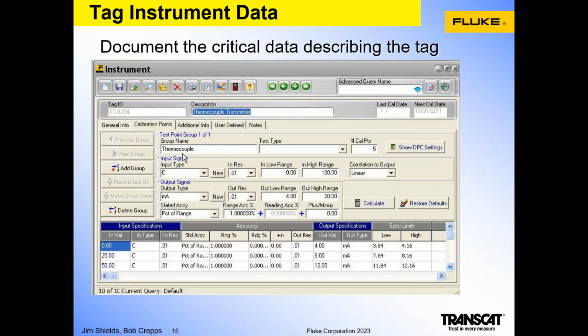Inside the information about this tag, we can see further information about its parameters. It's a thermocouple transmitter. Its input is measured in degrees C. Its output is a milliamp signal. It has a range of 0 to 100 degrees C. Output is 4 to 20. And the specification for the device, the error allowed, is in percent of range, and it has a 1% tolerance. Based on that information, you can see down below the allowable deviations for the milliamp signal based on those temperatures applied. These are the test tolerances and definition that will eventually be loaded into the documenting process calibrator to test the device in the field to determine if it's in specification.